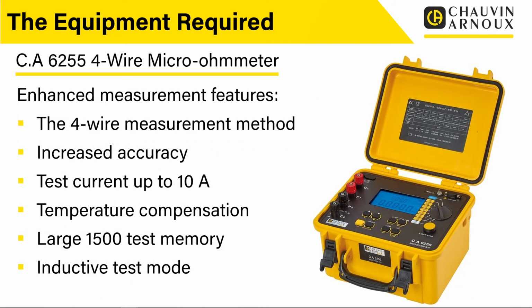Going up a step to its bigger brother, we're on to the 6255. Again, a 4-wire micro ohm meter. And this has got a few extra improvements above and beyond what you'd expect off the 6240. So it is 4-wire measurement. It's got increased levels of accuracy. So we're actually able to measure down to a micro ohm, so the actual levels of accuracy are improved. It still does test currents up to 10 amps, so it's still a 10 amp micro ohm meter technically.